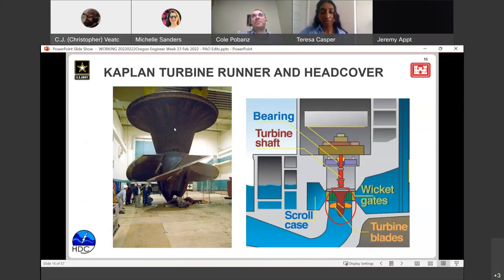So for turbines, we have two main types of turbines in the U.S. Army Corps of Engineers. This one is called a Kaplan, and they usually have 3 to 4 blades, and they can actually change the blade angle to go faster or slower depending on what the system needs. The picture on the left shows a pretty old Kaplan unit because again, most of these dams were built in the 40s, 50s, 60s. So most of these blades are being welded in place due to excessive maintenance issues like oil leakage, so they actually lose the functionality to change the blade angle, but the newer ones still have it.